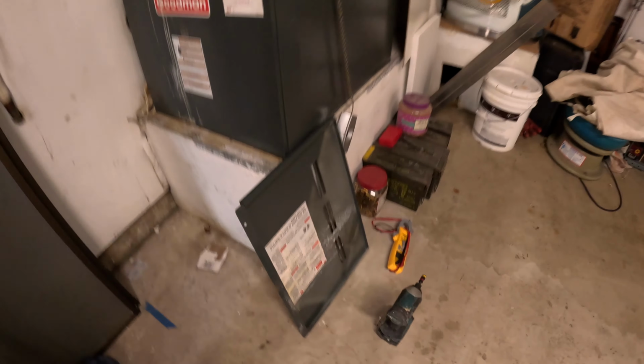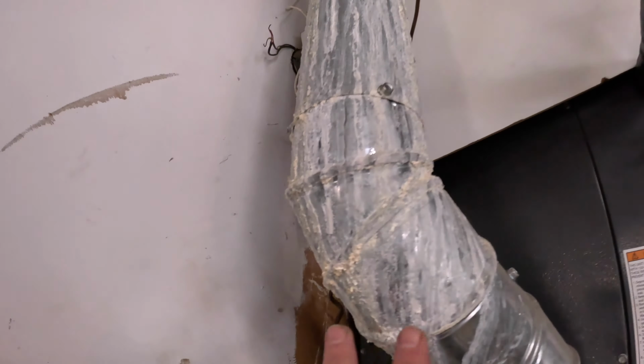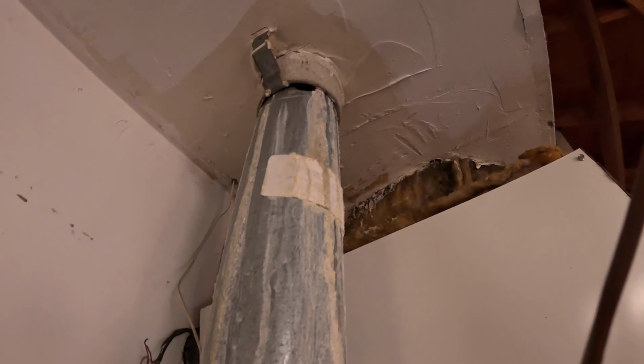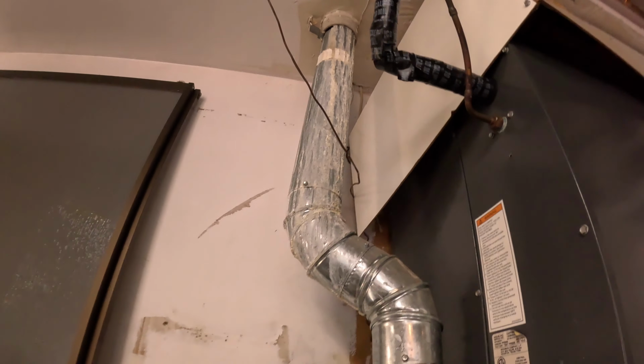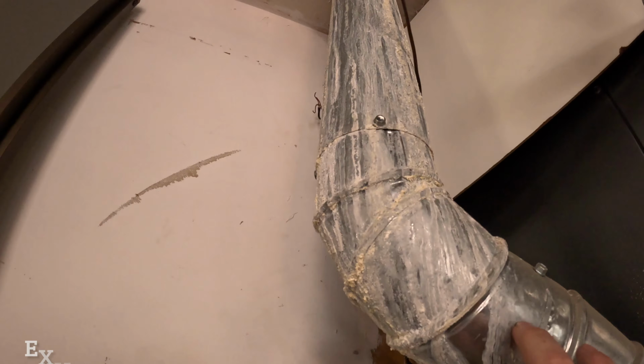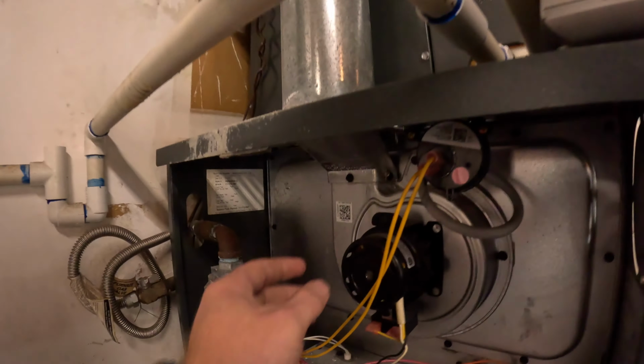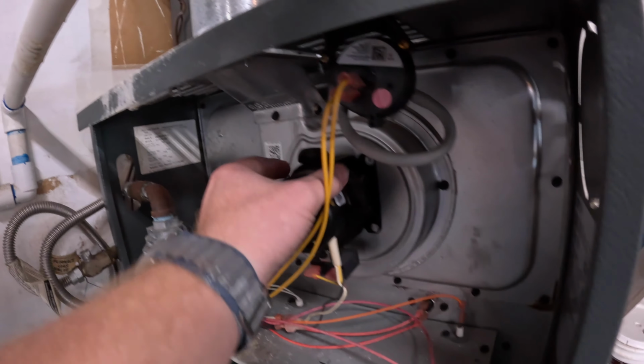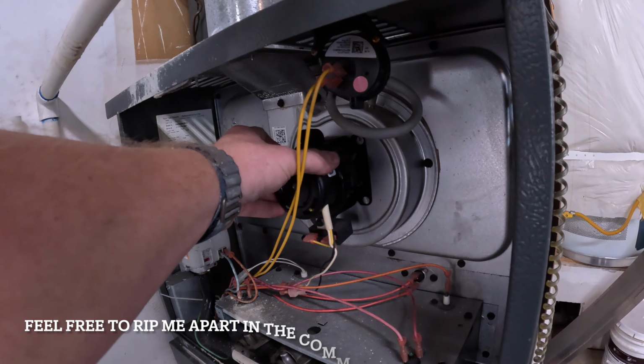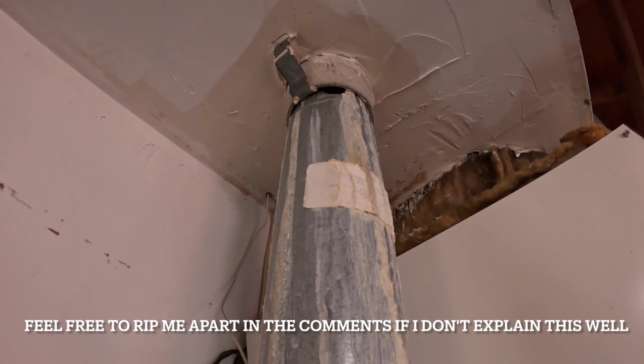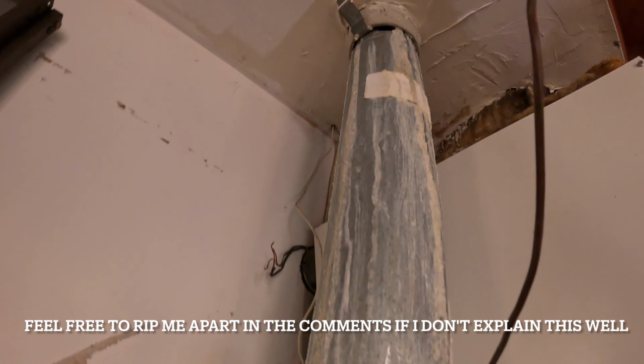I already took this off, but walking up, we already see that they tied this directly into transite. What actually happens is the temperature of these furnaces with this inducer draft motor is lower. When the exhaust hits it, it actually creates fluid that drips all the way down and comes into your furnace and causes issues with it.